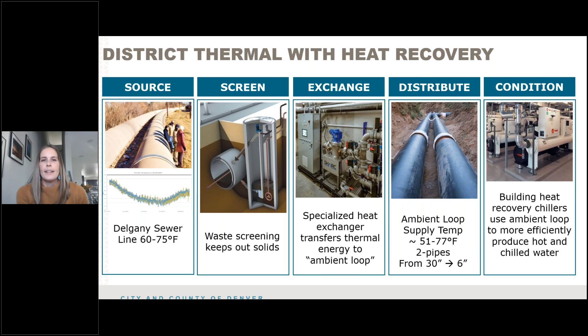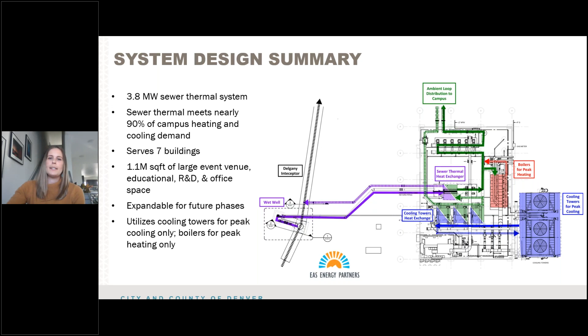So the sewer comes from the Delgany line represented there in purple and is exchanged to the green ambient loop. Then if the loop needs extra cooling at peak summer times, we'll get a cooling boost from a set of cooling towers that are outside. And then boiler heat is injected in red there during the peak heating times. So all in all, the system is 3.8 megawatts of sewer thermal energy. And then we're reducing gas heating by 90%. Cooling kind of stays the same, but about 80-some percent of the cooling will be just from the sewer thermal. And this will serve 7 buildings and over 1 million square feet of the campus footprint. And it's set up so that we can expand in the future and maybe add some extra features to the plant that can further boost efficiency. Next slide.